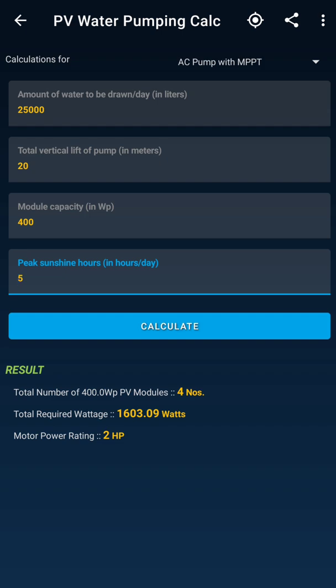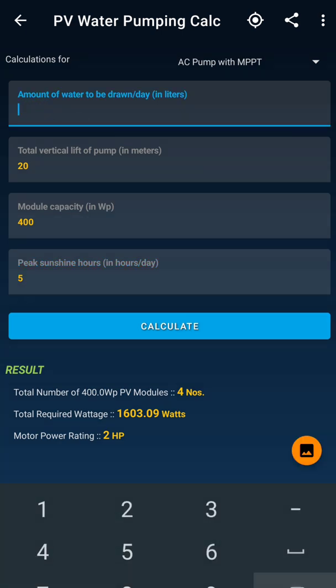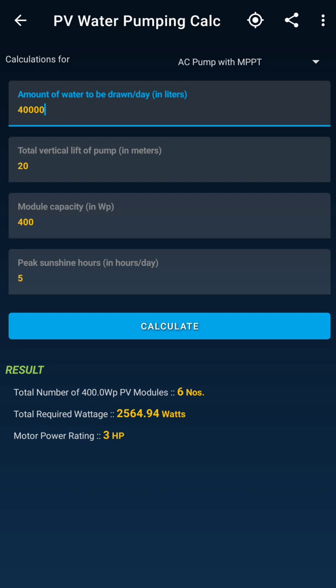Now let's say my water consumption increases — I have a bigger land and I need 40,000 liters per day. I hit Calculate and the moment I increase from 25,000 to 40,000 liters, the motor rating increases from 2 HP to 3 HP, and the number of modules also increases. In the same five peak sunshine hours, I want more water, so the pump power must increase, and more modules are needed to run a 3 HP pump.